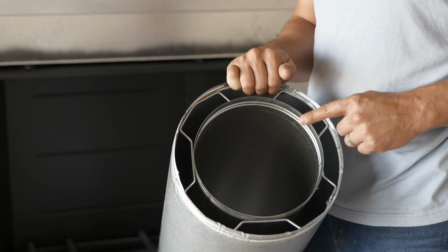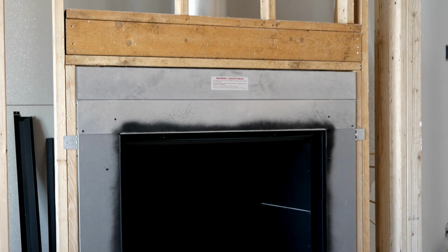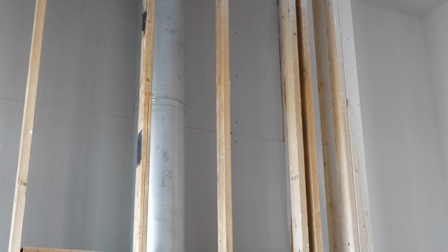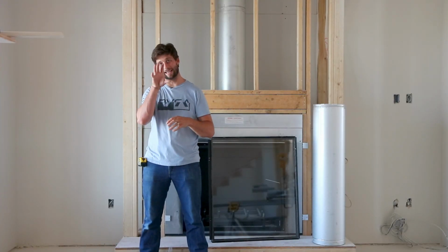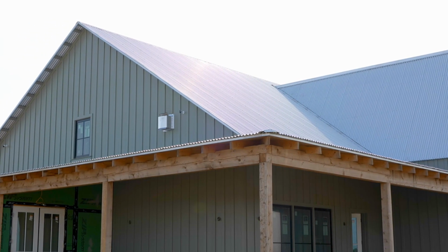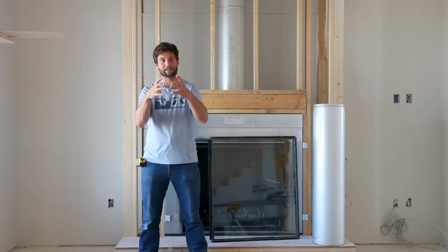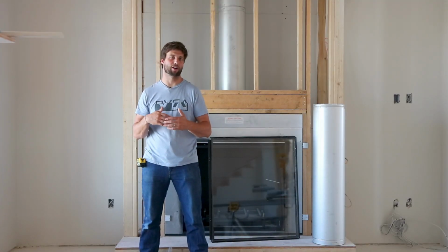I've got a coaxial tube that is coming from the outside to the inside of my house. It's pulling fresh air in from the outside, taking it down to my firebox, which is completely sealed from the inside air. It's burned with the natural gas, and then it's exhausted through the center pipe of this coaxial tube. It's a really cool system, this coaxial thing, because the inside tube is my exhaust and the outside is my fresh air. That means that I've got an insulated layer of about 1.5 inches to 2 inches on either side of my hot exhaust pipe, and because this air is moving, I'm always bringing in cool air, cooling down this whole assembly. So I don't need a big hefty chimney in order to keep the fire and the heat away from my combustible material. So that's what we chose to do in this build.